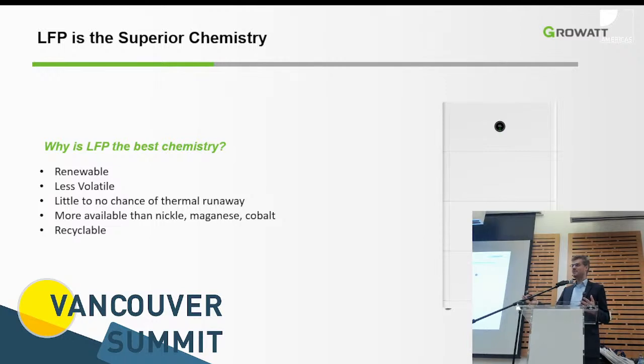And with the larger capacity in energy, you also scale the output power of the system. So if you only have 1 module, that's 2.5 kilowatt continuous, 4 kilowatt peak. If you have 2 modules, that gives you the 5 kilowatt continuous, 8 kilowatt peak. So our recommendation typically, if a customer already wants to have full home backup, is that the 10 kilowatt hour increment is probably the smallest energy size you want to give the customer, because 5 kilowatt hours, even if it's low cost, doesn't give the customer a lot of value. You have the same work with the disconnect switch and the transfer switch, the same work to install the battery, the same inspection, but then only giving the customer 5 kilowatt hours.